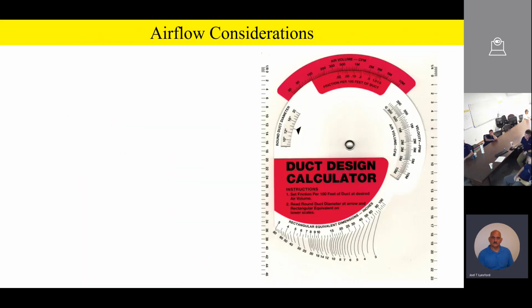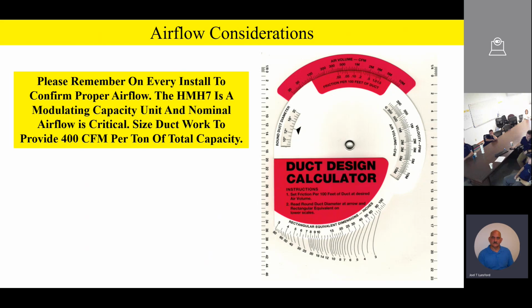All right, team, something we always want to remember on the HMH7 is to confirm proper airflow, because the HMH7 is a modulating capacity unit, and nominal airflow is going to be critical. So be sure and size your ductwork to provide 400 CFM per ton of total capacity. If I've got a 2-ton unit outside, I need 800 CFM. If I've got a 3-ton unit outside, I need 1200 CFM, and so on. So please consider that. Make sure your ductwork is in good shape and you're providing the airflow necessary for the tonnage of the outdoor unit.